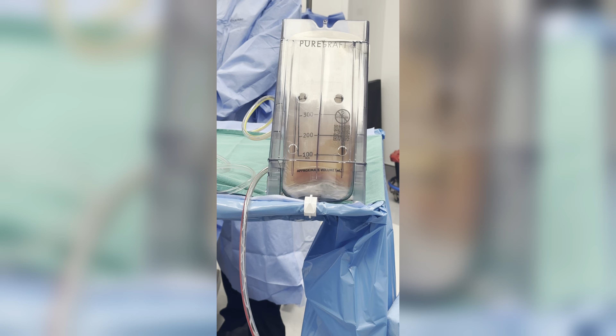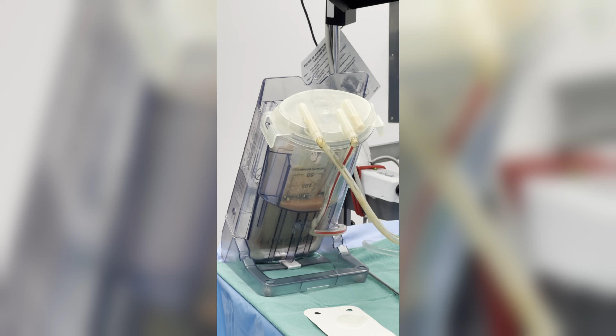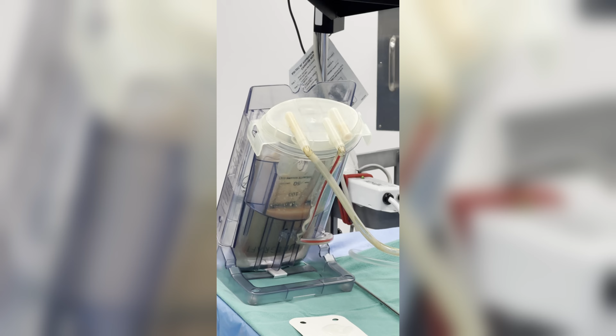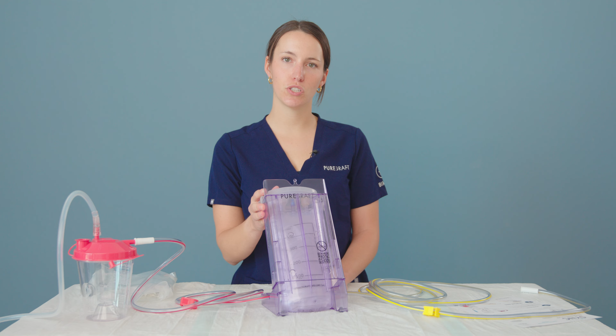You can harvest up to 500 milliliters of tissue into the Puregraft sink. You can use the scale on the integrated Puregraft filtration bag to estimate the total volume inside the Puregraft sink device. Keep in mind that the final purified graft volume will be about 50% less than what you see inside the Puregraft sink device, depending on your desired tissue purity. When you're finished harvesting, turn off your liposuction machine. Clamp the yellow patient tubing and the red waste tubing.